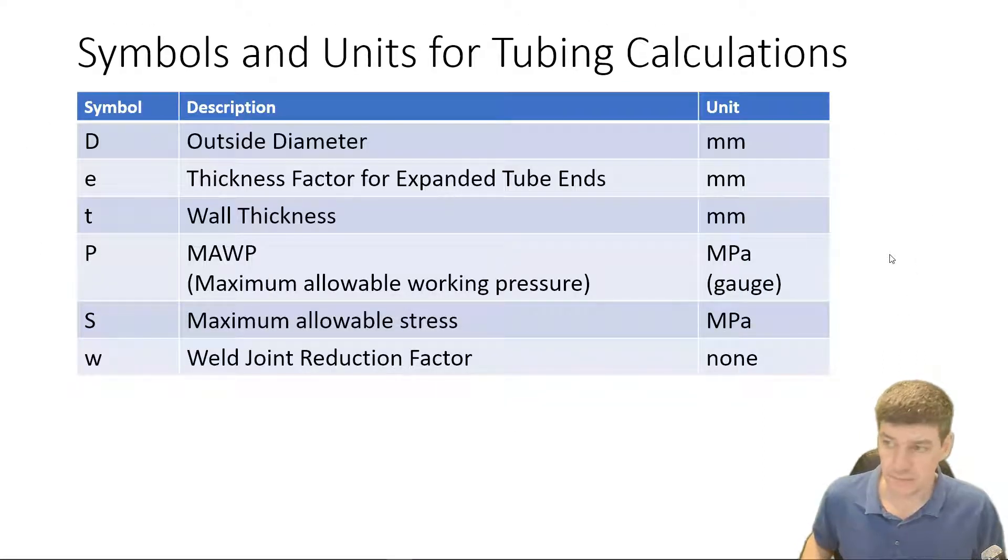Just as a summary for what we're going to need for tubing, we have a number of things. We have outside diameter D, this thickness factor, we'll talk about that, lowercase e, wall thickness T, P, capital P, MAWP, which is our maximum allowable working pressure. S, which is our maximum allowable stress. That's the value we'll get from our section 2 property tables that we looked at in the previous section. And then we have W, weld joint reduction factor.